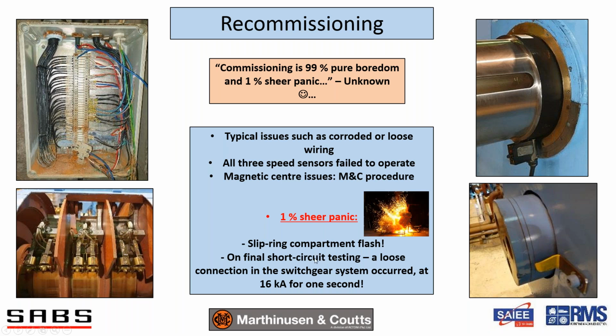And then I mentioned earlier, when NEFTA connected the switchgear in and did a 16, or I think it's 17 kA. I think I've got that one out by 1. That loose connection occurred in the switchgear, and it was a sort of reduced version of that, but it was a continuous arc for 1 second, because the test duration was 1 second.